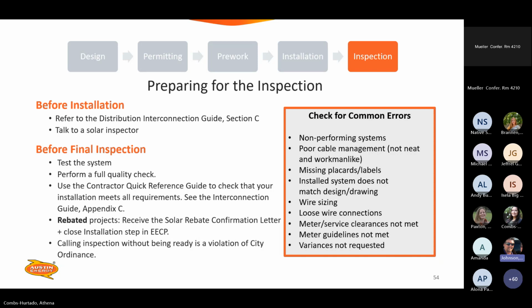They just don't work. That's not good. That will get you a fail very quickly. Poor cable management. So up on the roof, all the wires not being lifted up off the roof. Missing placards, labels, stickers. If you're missing all the red, yellow stickers, your red placard, if you have ESS, that is something that needs to be addressed immediately. Installed system does not match design or drawing. It will ask you to have the drawing redrawn for what was installed or install what was approved by the engineer on the drawings.